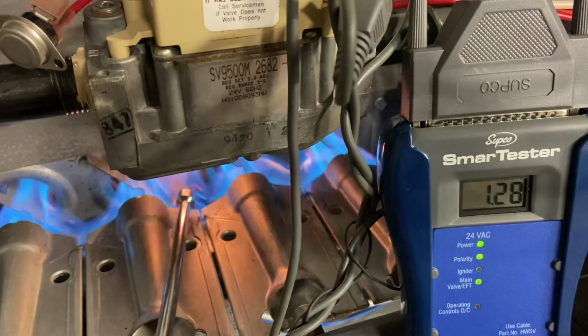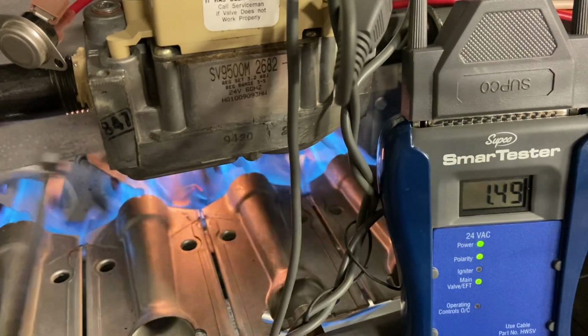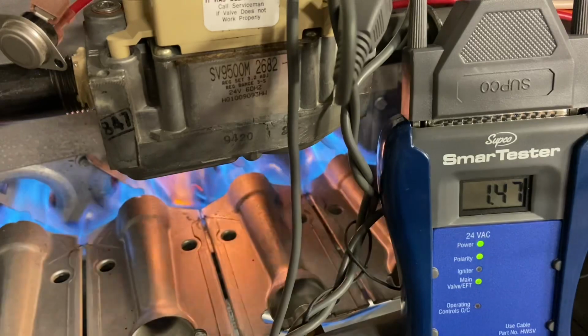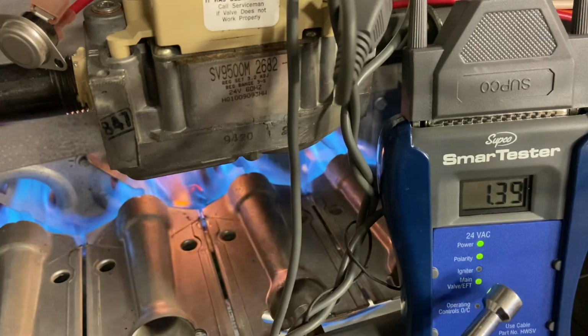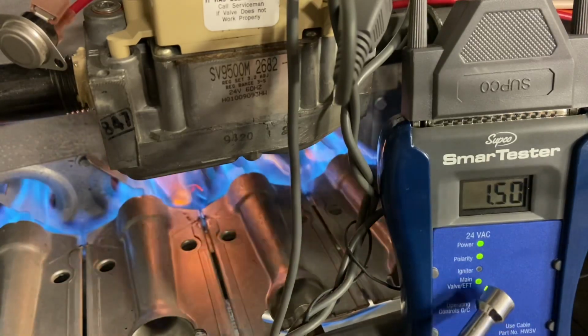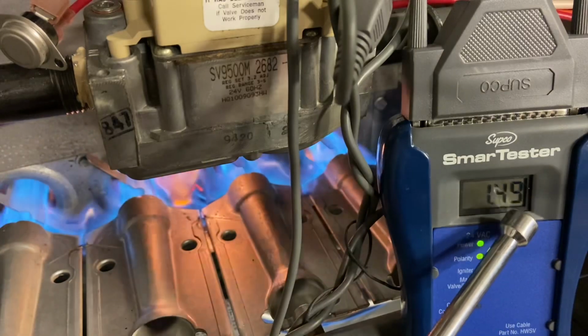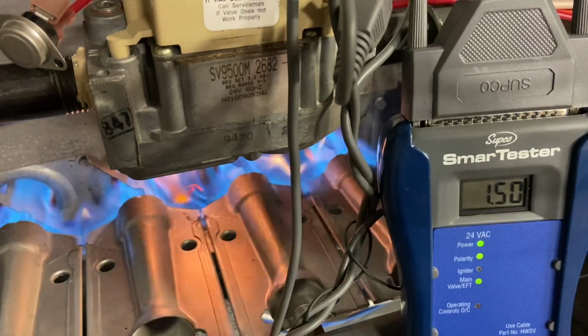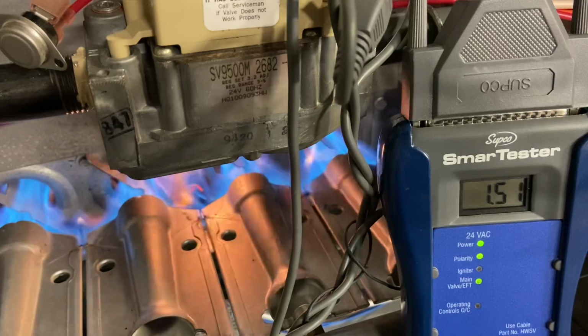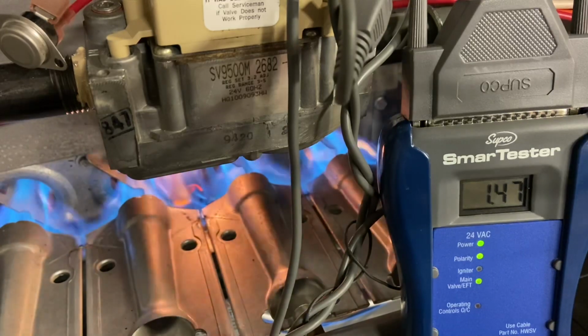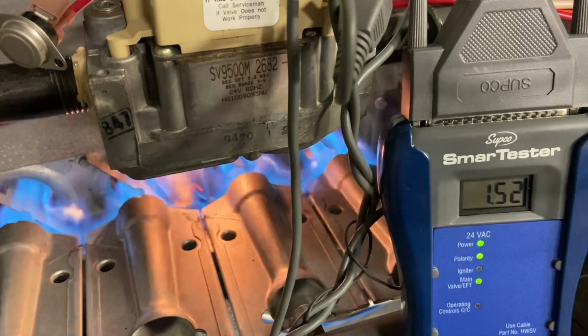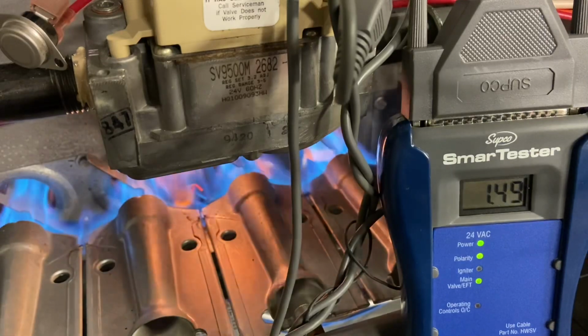The pilot over here is still burning. We did have to remove the safety plate to get the view in. On this side, we can see that the igniter had gone off. We have our main valve open, and this is giving us our flame sensor reading, so how many microamps we're pulling. Once the furnace heats up, the IFC should bring the blower on, but this IFC is not working correctly.